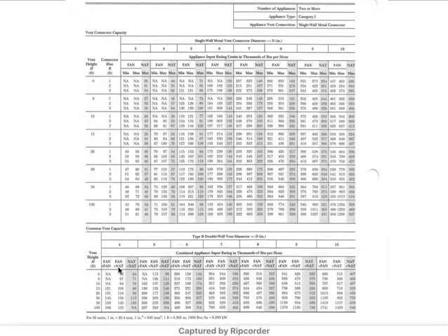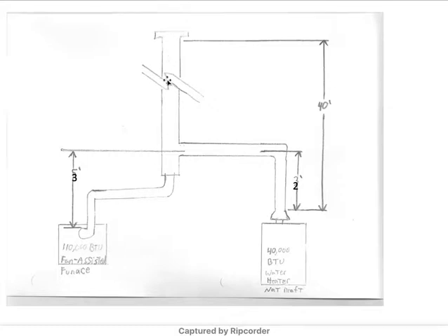So we're in fan plus NAT. We had a 40,000 BTU natural draft and 110,000 fan assisted. So that gives us fan plus NAT of 150. But first we have to go to vent height, 30 to 50, so we go to 50. We need to find a fan plus NAT of 150,000 BTUs. We don't get anything until we get to 5 inch. So 5 inch it is. Let's look at that one more time. This here would be 5 inch. A 5 inch B-vent, that's what your chimney would be.